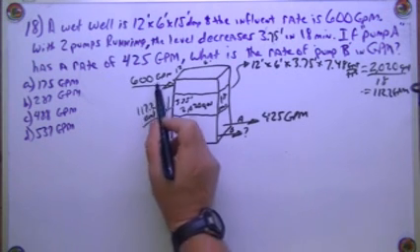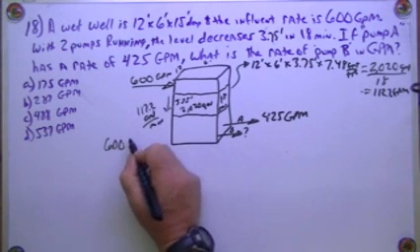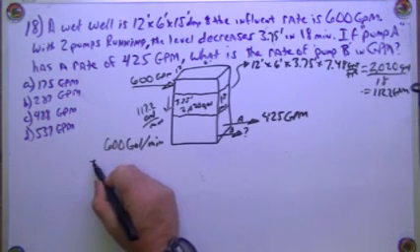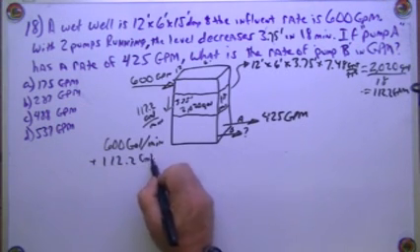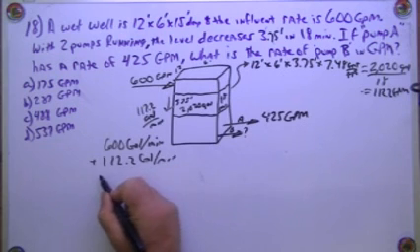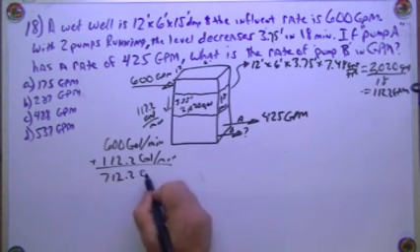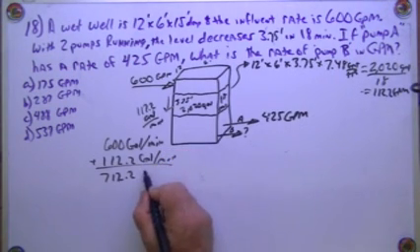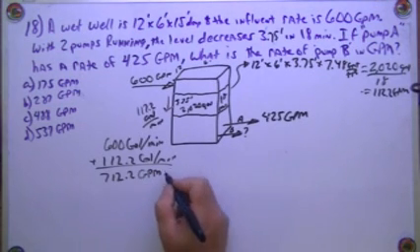112.2, so the total pumping rate is going to be 600 gallons per minute plus 112.2 gallons per minute, going to be 712.2 GPM. So that's total pumping.